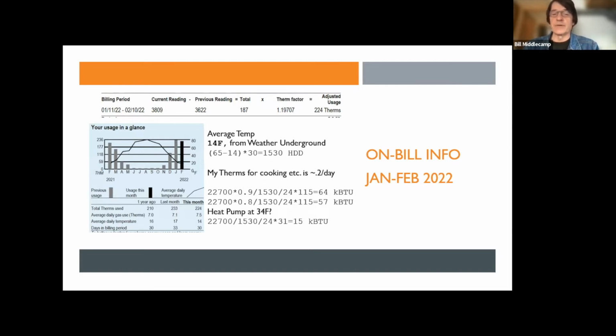And that's what the heating contractors wanted to put in my house. Now, there were some problems with that, and we'll get into that later. But the next line in here tells you what number you would come up with if you had an 80% efficient furnace. Instead of 0.9, I used 0.8. And then I have a heat pump now. That's a recent addition to my house. And it's set up to run whenever the temperature is 34 degrees or higher. So one of the questions I had is how much heating do I need in that heat pump in order to be able to heat my house when the temperature is 34 degrees. And you can see using just a smaller rise that my need would be 15,000 BTUs. Next slide, please.